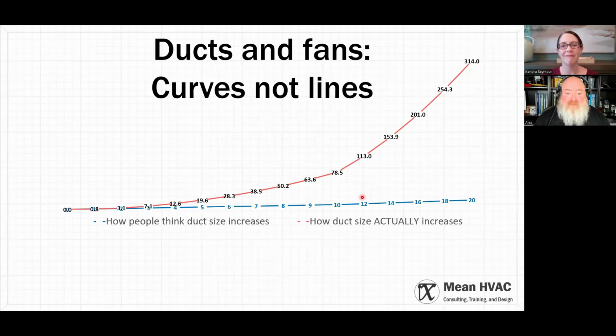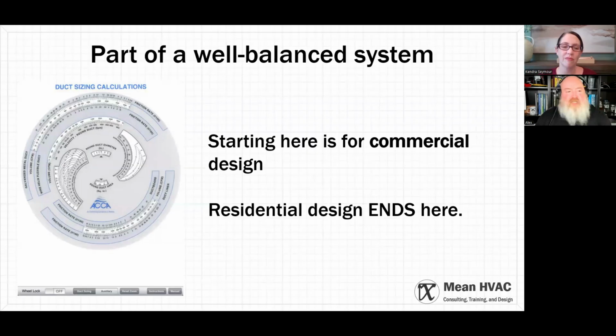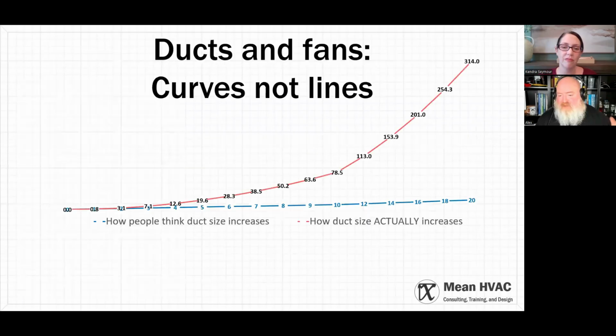When you size things by common sense rules, airflow can get away from you fast. The old rule of thumb, really the rule of the wheel, was to use a slide rule wheel and pick a specific number to size all of your ductwork. You dial in the number, find your airflow, and that's your duct size.